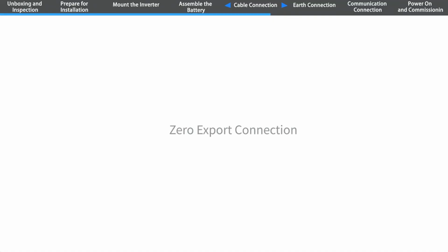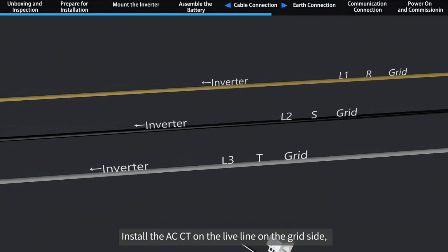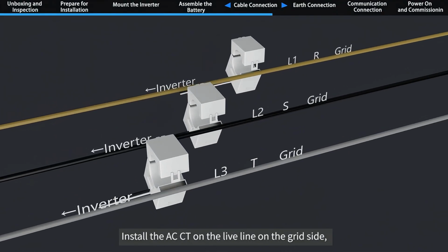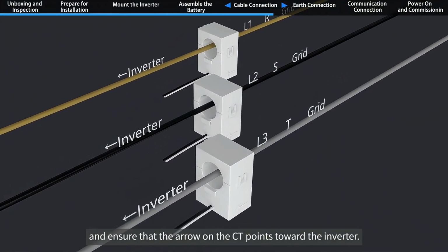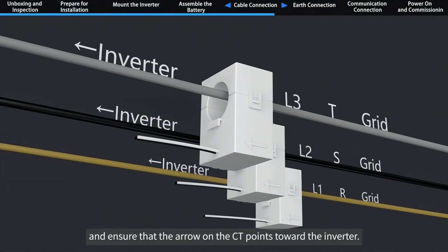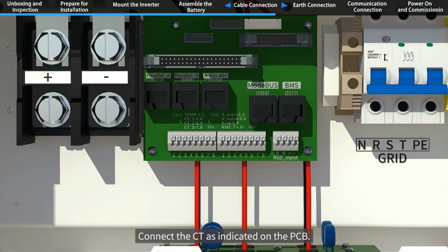Zero Export Connection. Install the AC CT on the live line on the grid side, and ensure that the arrow on the CT points toward the inverter. Connect the CT as indicated on the PCB.